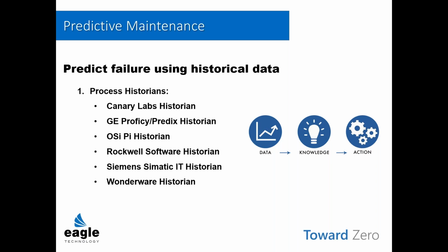From a maintenance perspective, we can use that data to not just look at something going out of tolerance in real time, but now we can go back and look at it historically and begin to mine that data, looking for trends and things that have happened more than once, correlating the event with the actual data itself. This allows us to set even more intelligent alarms and alerts for the maintenance staff to go take a look at.